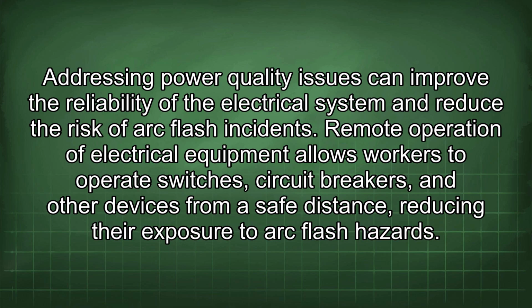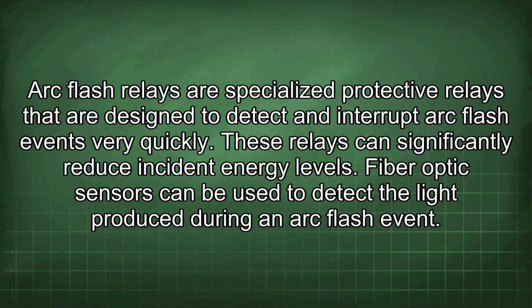Remote operation of electrical equipment allows workers to operate switches, circuit breakers, and other devices from a safe distance, reducing their exposure to arc flash hazards. Arc flash relays are specialized protective relays that are designed to detect and interrupt arc flash events very quickly. These relays can significantly reduce incident energy levels.